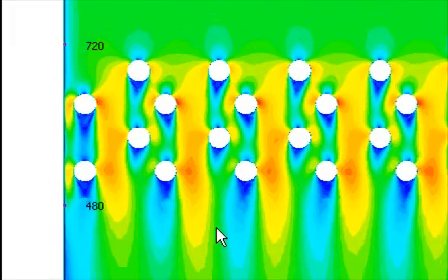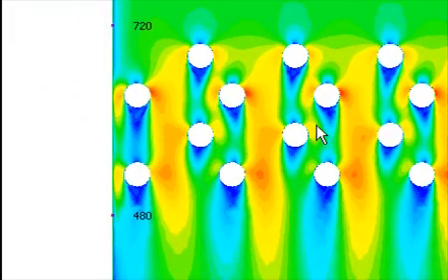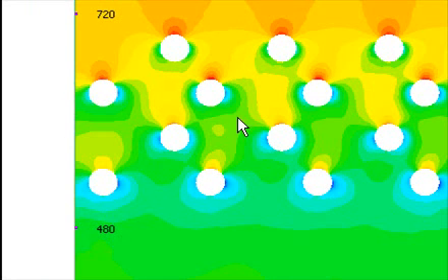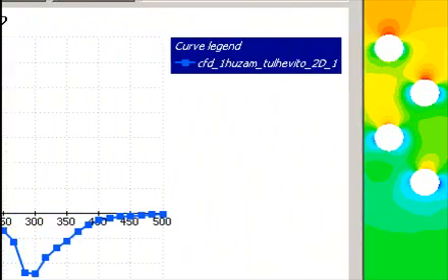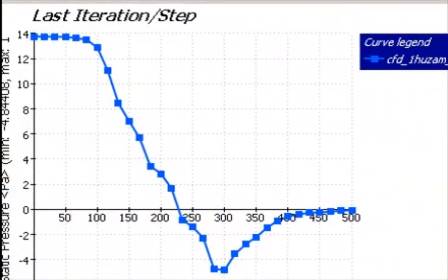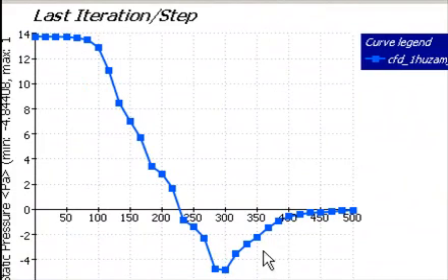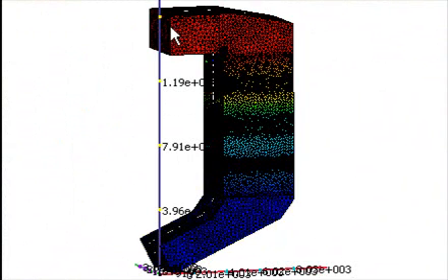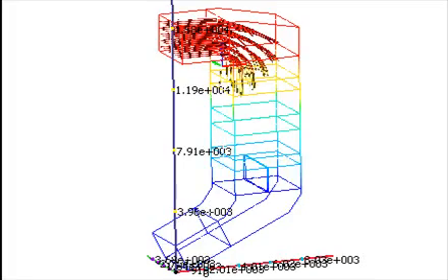From these simulations, the pressure loss of the flue gas in the given tube bundle can be read in a jiffy. The pressure loss of the whole bundle of a block now is just a question of multiplication. For example, it is 96 pascals for the superheater. Building the coupled fluid flow and heat transfer simulation this way and the proper mesh ensure the accurate velocity and temperature results. These are the keys to determine accurate pressure loss data of the steam generator.